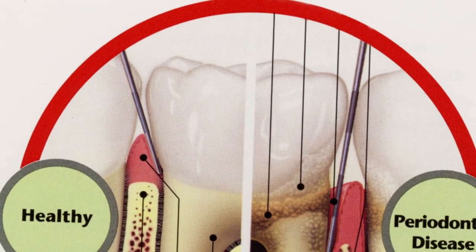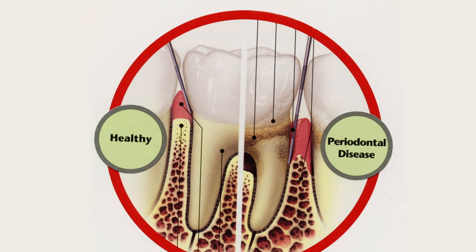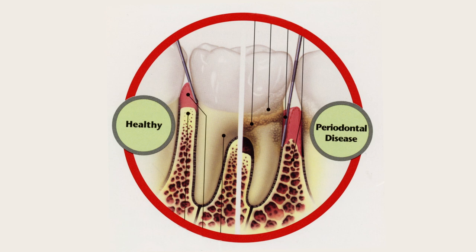Clearance specifications vary continually during scaling and root planing according to alterations that accompany each change in position of instrument angulation or tooth contour. With normal use of a curette or scaler, instead of finding significant rounding at the cutting edge itself, it is usually a progressive loss of clearance through abrasion that dulls a scaling instrument in use. There is no need to resharpen the cutting edge itself. One needs only to restore proper clearance on the lateral side of the cutting blade.